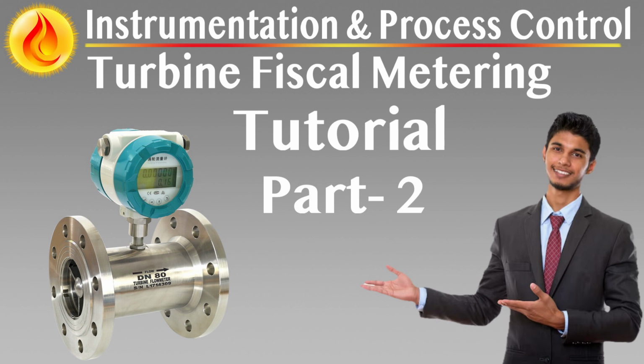All analog to digital conversions must meet an overall uncertainty threshold of less than 0.020%. Computation and digital output uncertainty must not exceed 0.001%, ensuring that the metering logic maintains high precision from signal acquisition through final calculation.